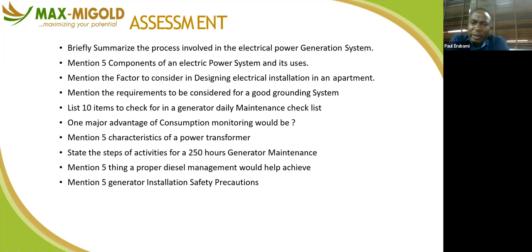Have you been able to determine the exact load that is required in that estate or facility? If you determine it, you may not need that 500 kVA as well. Just because it's 500 doesn't mean the 500 kVA is optimally utilized. I want to give you an assignment: determine the load at peak period and off-peak period, so that you know whether it is even good to be using that or a lesser generator. Once you determine that, you know what to do.